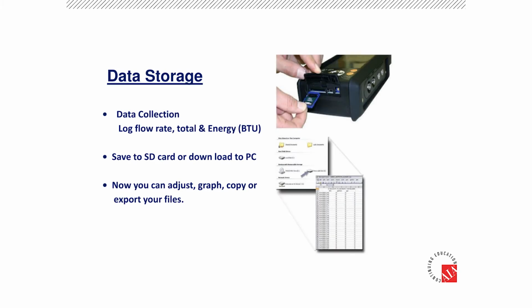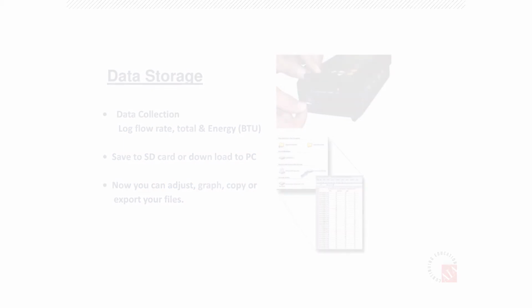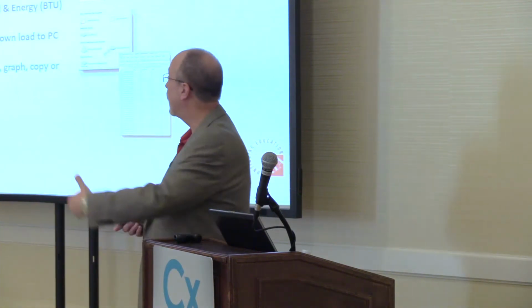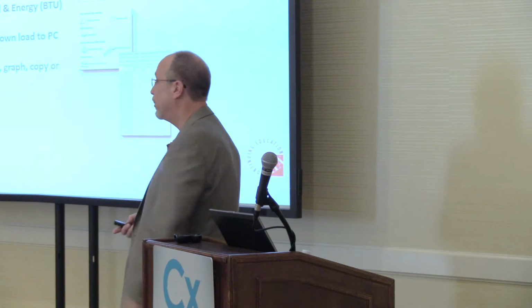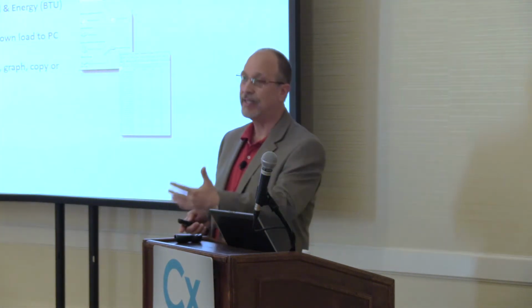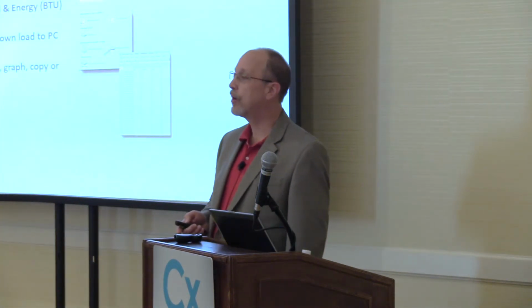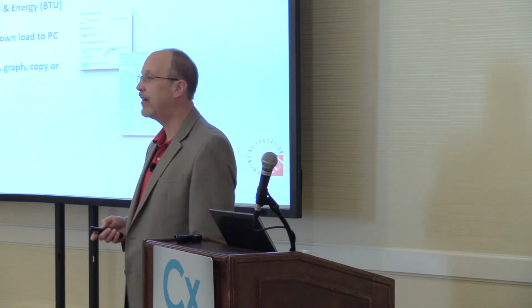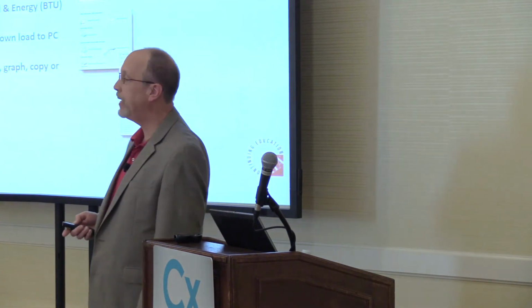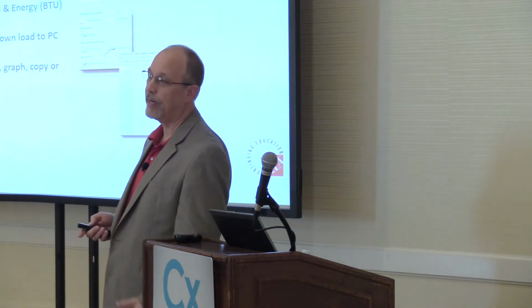Now, when you do your submetering, what are you going to do with the data? So if you do your testing there, you need to harvest your data. And most of the newer technologies all have data loggers on them. So you can store your records on your flow meter, and in a lot of cases, then you can download your flow meter. Some of the meters now have SD cards that you don't even use software cables. They save it as a CSV file, put it in your laptop or PC, turn it in Excel, there's your data.